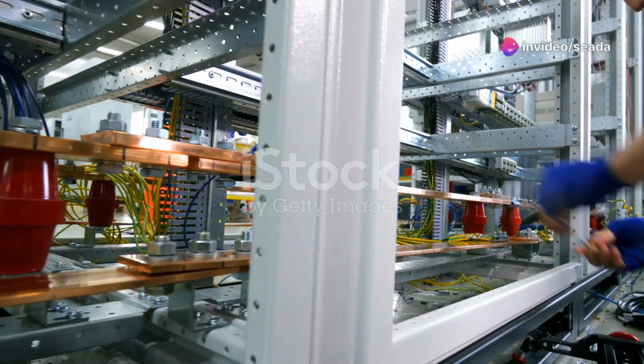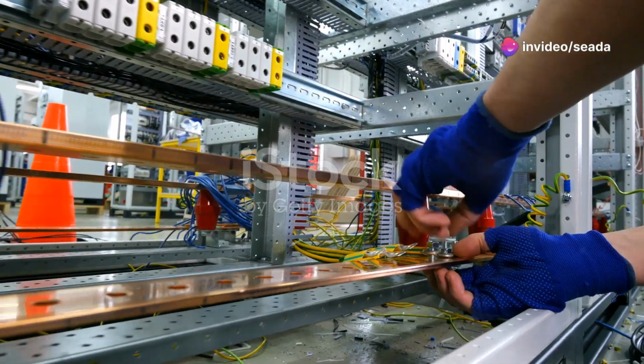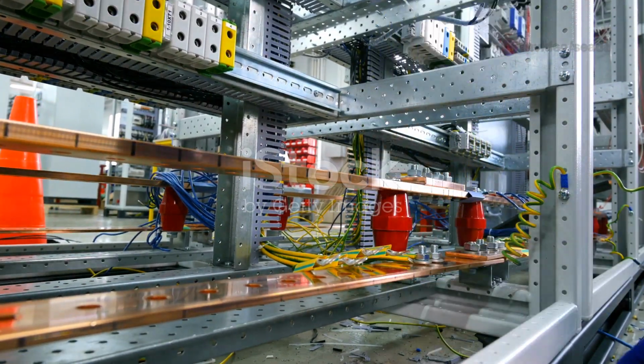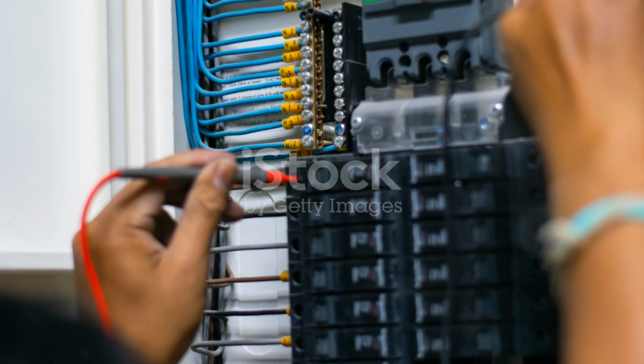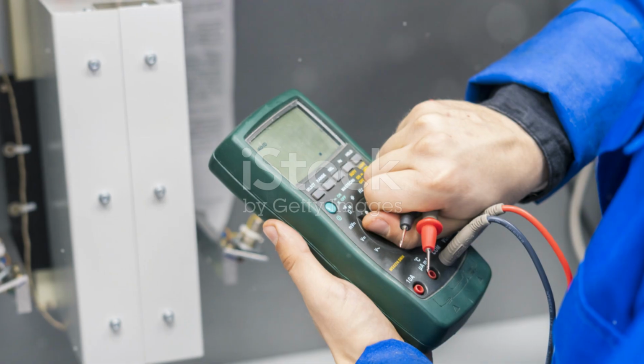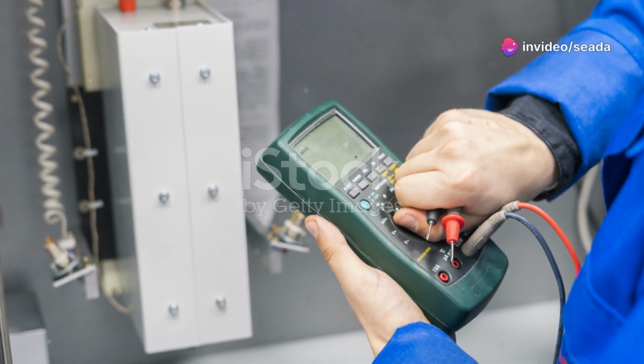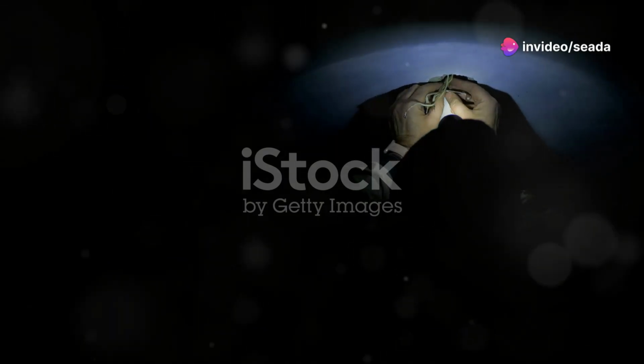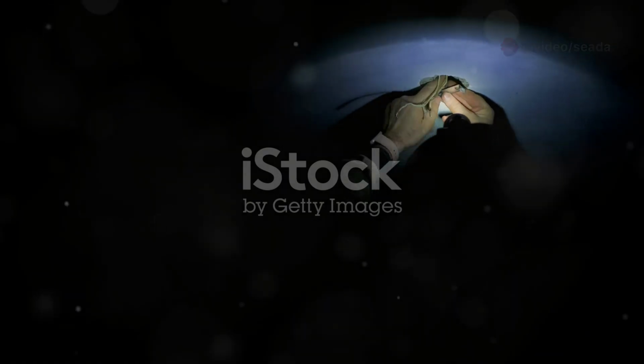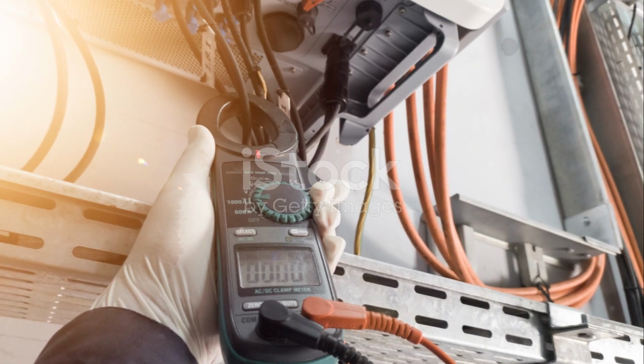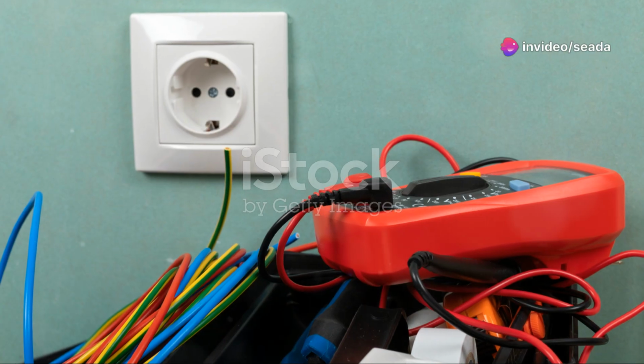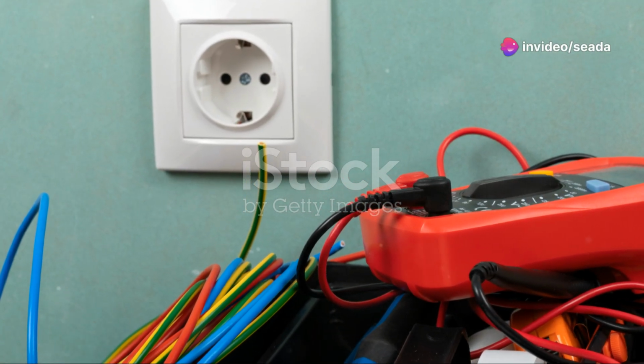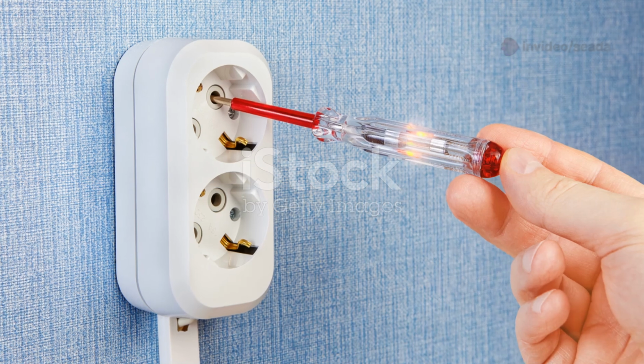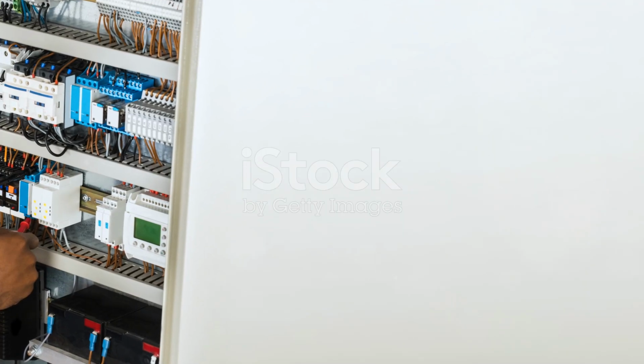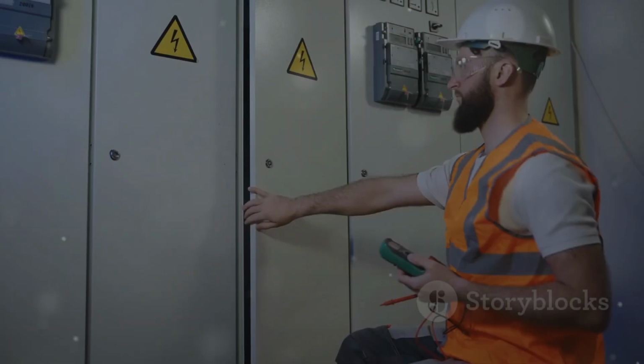Always reconnect wires securely after testing. Loose connections can cause future faults or even be dangerous. If you're unsure, stop and call a professional. Electrical work can be hazardous, so don't take unnecessary risks. Methodical testing leads you to the source. Don't rush. Careful troubleshooting saves time and prevents mistakes. Document your findings as you go. Keeping good records helps if you need to revisit the problem or call for help. Safety and accuracy are everything. Always respect electricity and use your multimeter with care for reliable results.